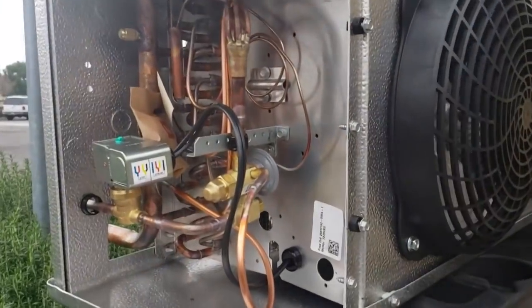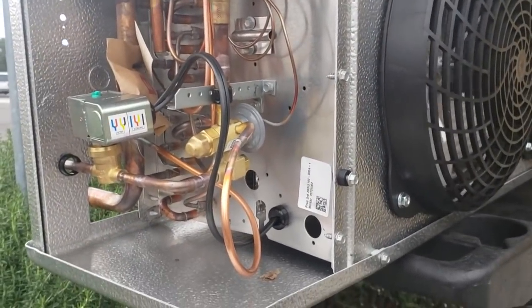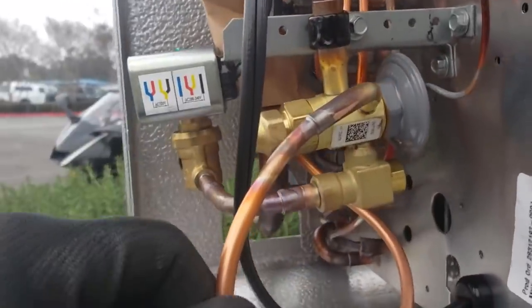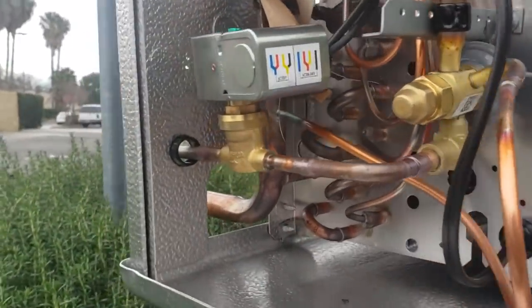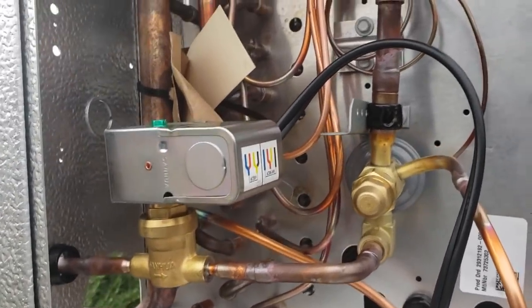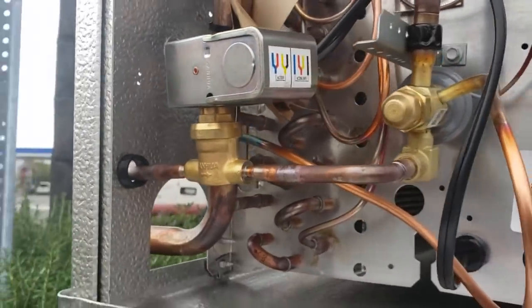We're getting ready to pull this guy out — we're going to change it. Old, old coil. As you can see, this coil comes prepped. Heatcraft was smart and they put a Sporlan TEV in there, but they used some off-brand weird solenoid valve. Not a fan of that.